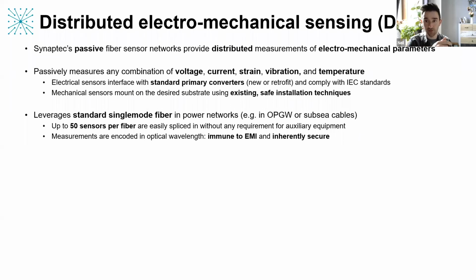So that voltage, current, strain, vibration, and temperature. And those are simply spliced in at the measurement location. Because they're completely passive, there's no requirement for any auxiliary equipment like power supplies, active telecoms, or housings, or things like that, or GPS access. So that makes it much more lightweight, it takes up much less space, and is generally faster and simpler to install than conventional methods would be.